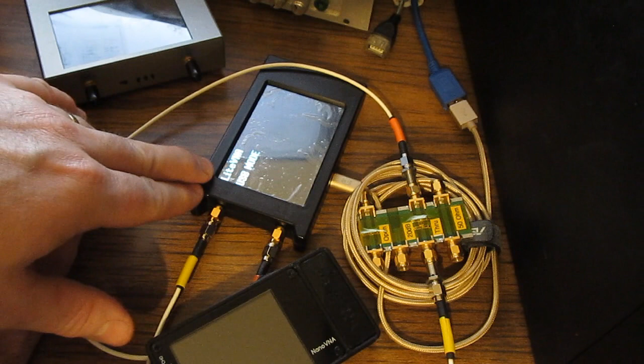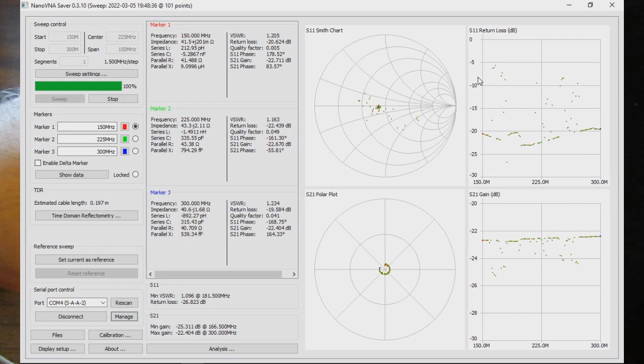It's fine. One of the things I should mention, the reason that I'm running this at 150 megahertz, again, the device has two synthesizers. If you're running the lower frequency synthesizer, it slows down the sweep rate quite a bit. And again, remember that IF bandwidth filter he's got in there. So the lower the frequency that you're looking at, the longer the sweep rate. So with this, I don't really see a way to speed this up. Unfortunately, of course, if you were tuning a filter and you're only seeing an update once a second, that's going to be pretty rough.